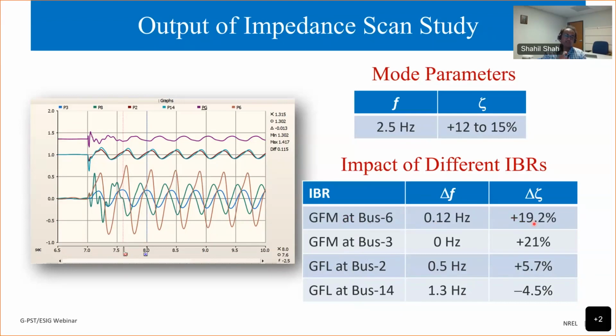So just looking at the oscillation magnitude will not tell you whether a particular IBR plant is a positive or negative contributor, because the oscillation magnitude can be high if the event exciting those oscillations is closer to that plant, or it might simply be high because that IBR plant is participating more in that mode. But participating more doesn't mean it's a positive contributor or that it's actually adding damping. So if we take this brute force approach of just curtailing IBRs where we have high oscillations, sometimes we may actually be reducing the damping and making the system more vulnerable to these oscillations.